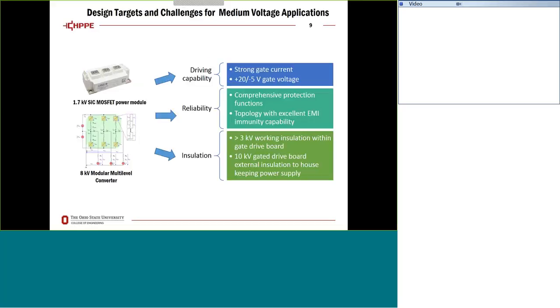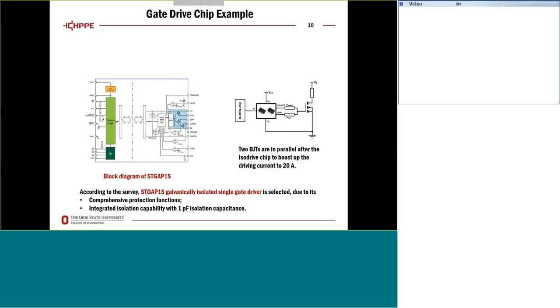And again, today I want to focus on the medium voltage device for high voltage, but I want to start with an example of devices for medium voltage applications. For example, in this case, we are looking at 1.7 kV silicon carbide for an 8 kV modular multilevel inverter, and we still have very stringent isolation requirements for this kind of application. The gate drive designed for this, later on I can explain, still needs to have a high insulation requirement, and the grounding scheme for this gate drive actually is very applicable to the medium voltage device too.